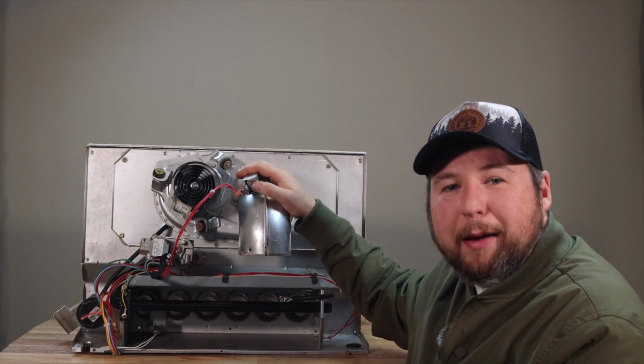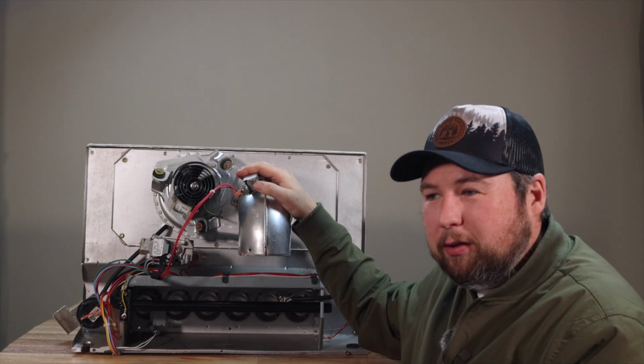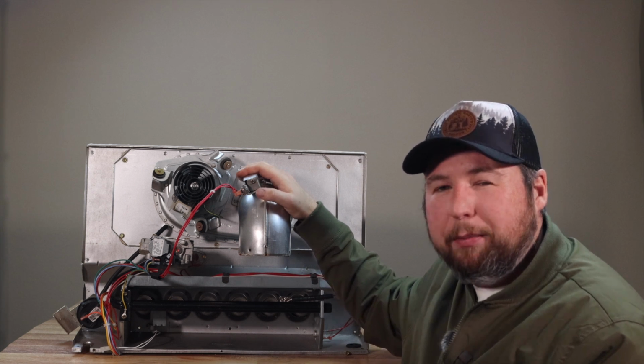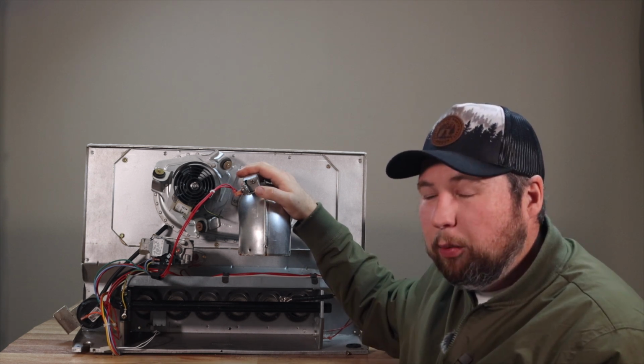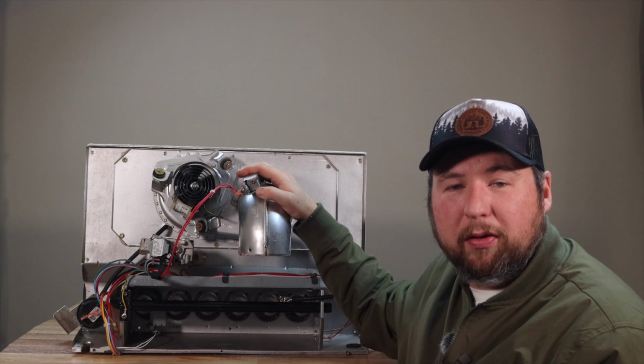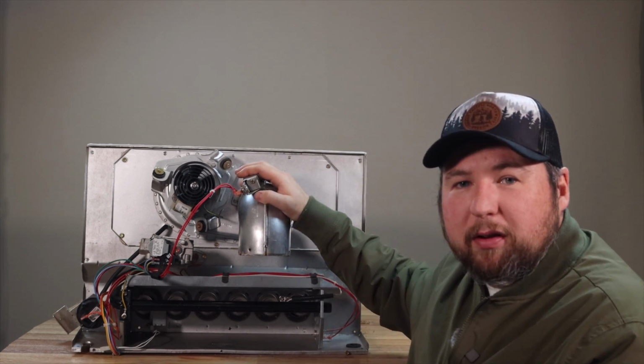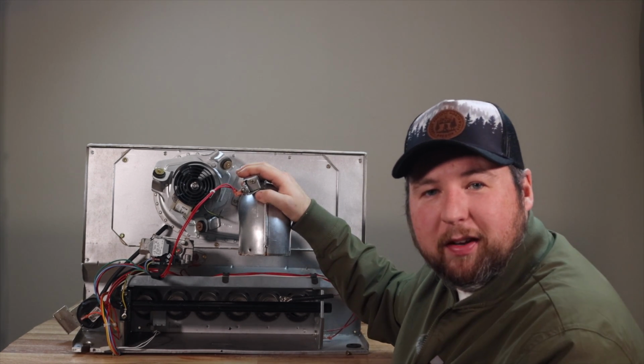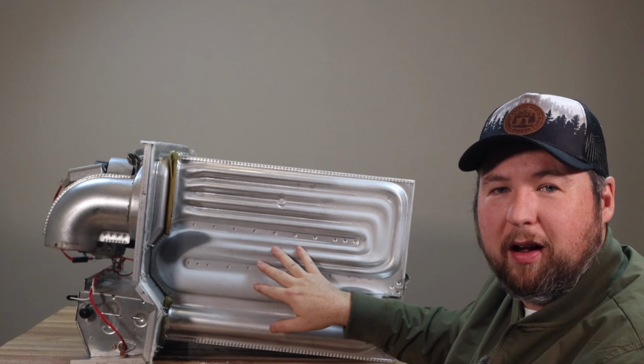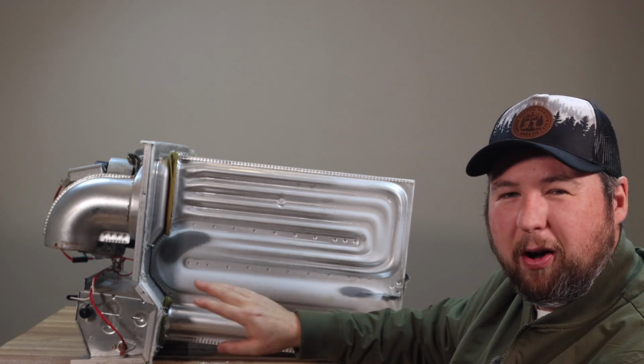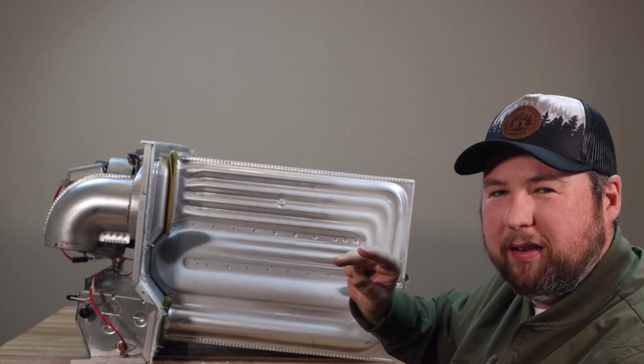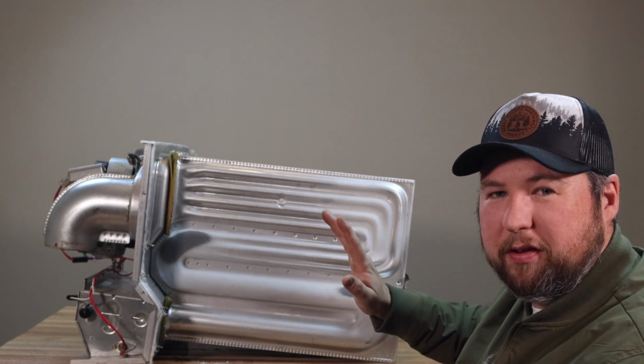So we're going to go over the types of heat exchangers now. There's basically three major types. There's the one I mentioned already, which is on the natural draft furnace. That's called the clamshell. Then you have what's called the serpentine. So let me show you what a serpentine looks like. This is a serpentine off of that Carrier. They're all slightly different, but they all basically follow the same principle as far as design goes.